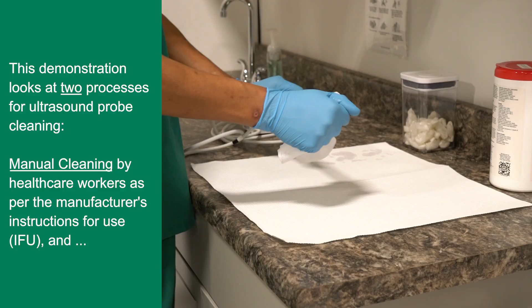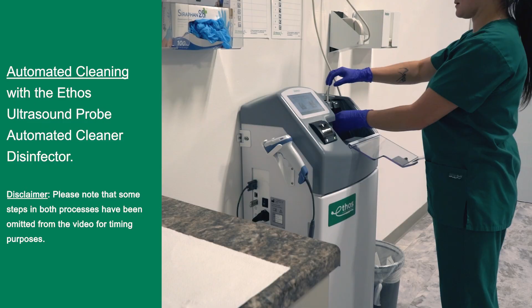This demonstration looks at two processes for ultrasound probe cleaning: manual cleaning by healthcare workers as per the manufacturer's instructions for use, and automated cleaning with the Ethos Ultrasound Probe Automated Cleaner Disinfector. A fluorescent dye is used to soil each probe and allow us to see the results and check the effectiveness of each cleaning. 3 separate ultrasound probes are featured. Let's get cleaning.